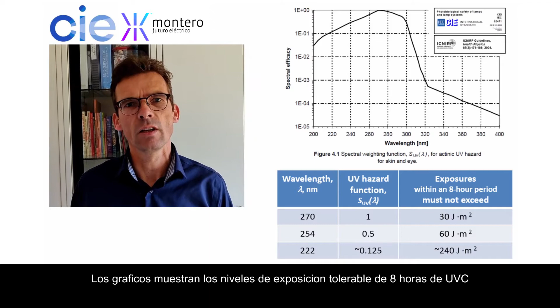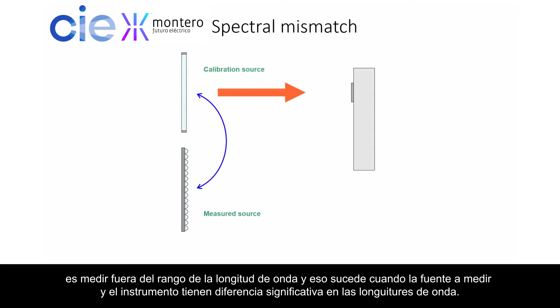Tony, as our Division 2 director, we know that you're the expert on measurement. What are the issues or concerns that might arise with measurement of germicidal UV? Measurement of ultraviolet radiation is difficult, and it's very easy to end up with large errors in our measurements. The most significant source of error likely to be encountered in practice is spectral mismatch, and this occurs when the calibration source and the measured source have significantly different spectra.